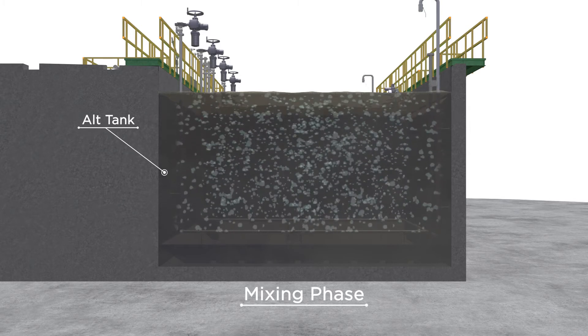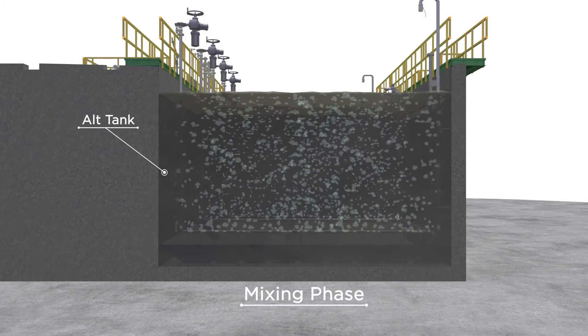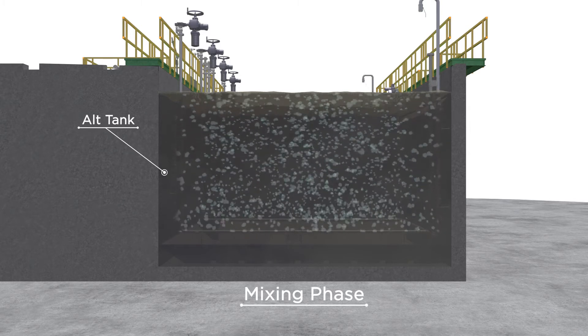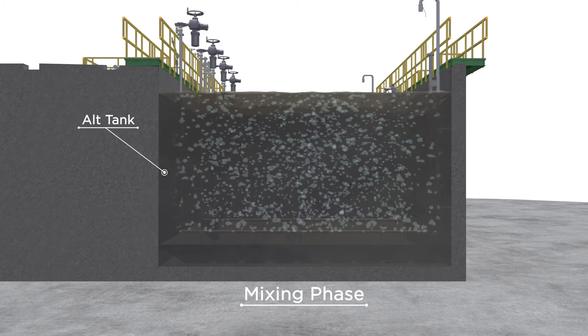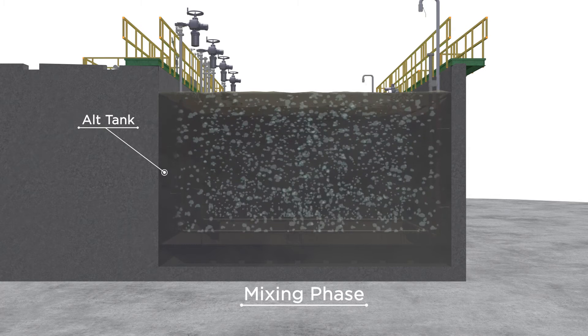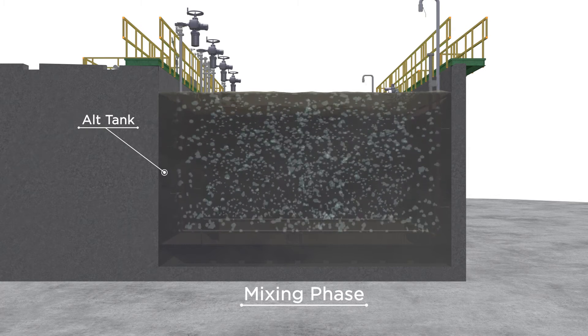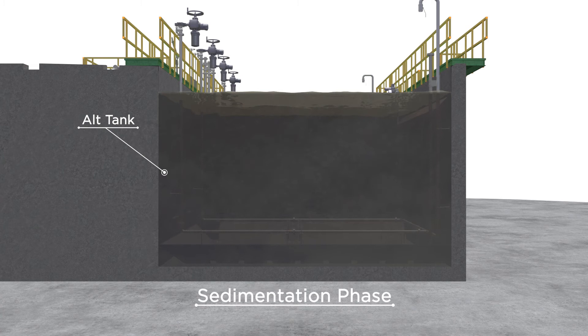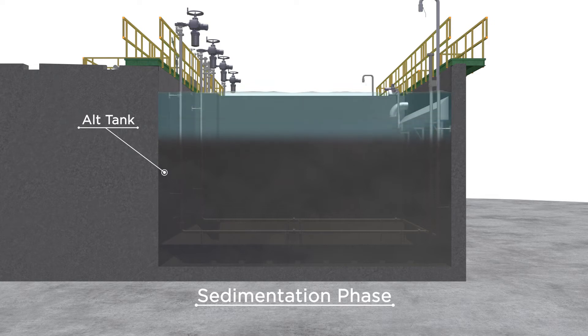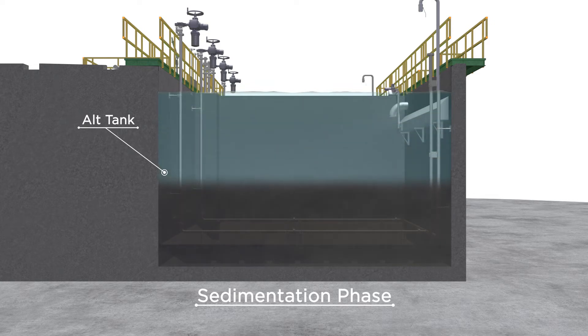During the mix phase, the Alt Tanks are mixed by a roll current induced by coarse bubble aeration for a few minutes. High mixing intensity homogenizes and re-aerates the anoxic sludge blanket. Upon entering the sedimentation phase, the settling sludge blanket promotes the formation of a floc filter and allows fine particle removal and the development of a dense bottom sludge layer.